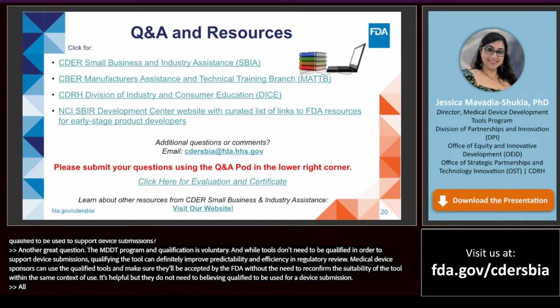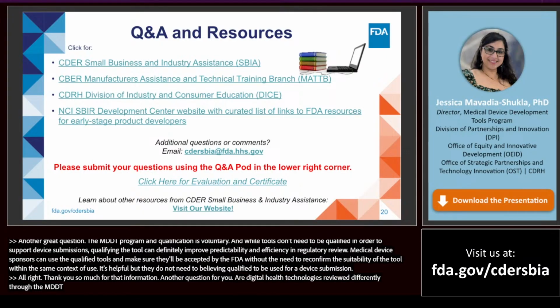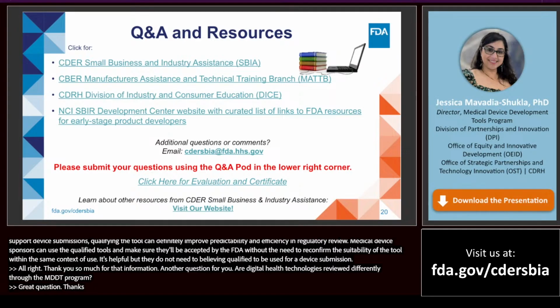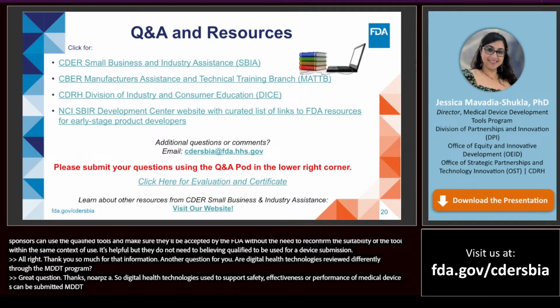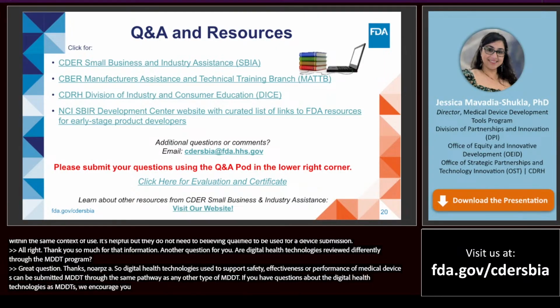Right. Thank you so much for that information. Another question for you. Are digital health technologies reviewed differently through the MDDT program? Great question. Thanks, Nora. So, digital health technologies that are used to support safety, effectiveness, or performance of medical devices can be submitted to the MDDT program for qualification through the same pathway as any other type of MDDT. If you do have questions about digital health technologies as MDDTs, we encourage you to contact the MDDT program through our email inbox at mddt@fda.hhs.gov. Thank you.